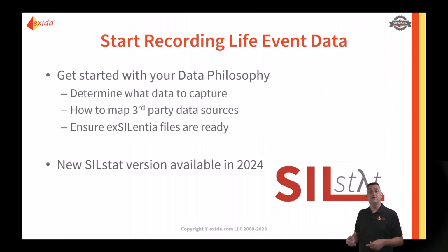And lastly, if you're already a user of exSILentia, you can see how this analysis and design and implementation information can be easily transferred to the operational phase for use in SILstat. If you want to do that, you want to make sure that your exSILentia files are ready to go. And what I mean with that is, if you look, for example, at a layer of protection analysis, in the LOPA tool, you can place those layers of protection in the order of which they will be executed. So maybe an operator responding to an alarm is the first one, followed by a safety instrument function, followed by a pressure relief device. By making sure that those layers of protection are in the right sequence of protecting against the initiating event that starts the whole sequence, we can import that information.